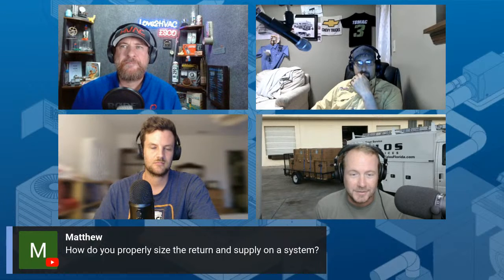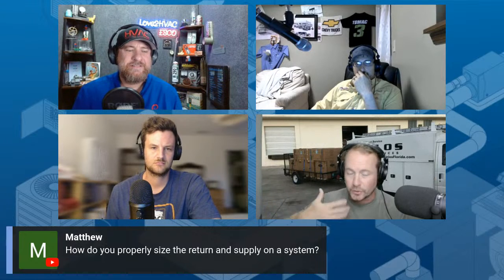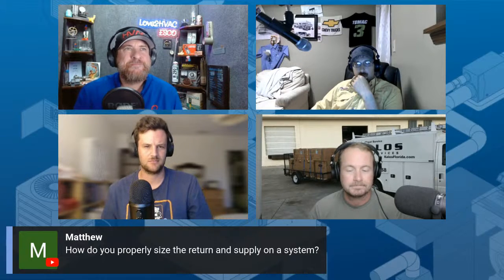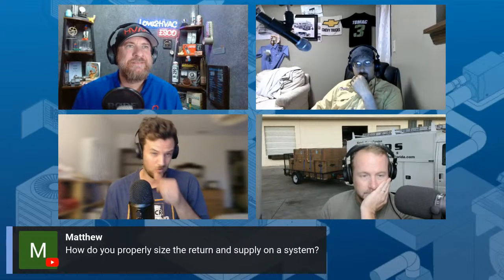Still use hand dampers in your supply ducts. Don't bet your life on your calculations. You can oversize ducts all day long, even on your branches, as long as you're using manual dampers and sizing your grills properly. Your grills have to be sized based on throw and mixing, but you can oversize your ducts, just have adjustable manual dampers in place, because Manual D sizes for the longest run.